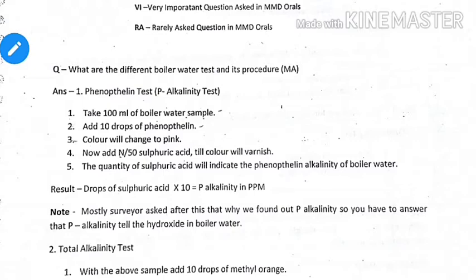The alkalinity test will determine what amount of alkalinity is present in the boiler water — whether the boiler water is acidic or alkaline. If the boiler pH is low, the water can become acidic due to the action of dissolved oxygen and chloride, forming corrosion pits.